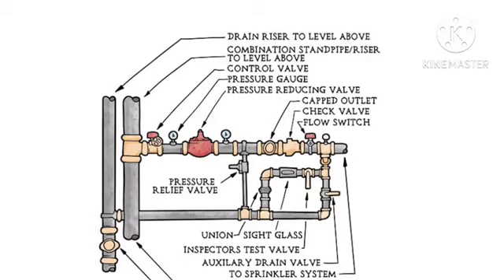A breakout of a floor control riser assembly. The following is a full arrangement for a combination standpipe sprinkler riser where high pressures necessitate a pressure-reducing valve at each level. While every element in this specific arrangement is certainly not a necessity on every project, here are some considerations that go into the requirements and considerations for a layout like this.